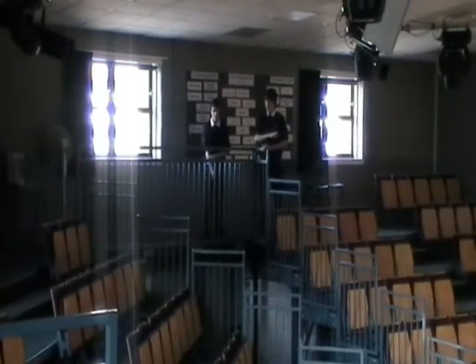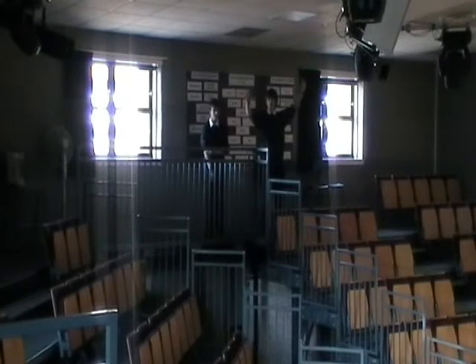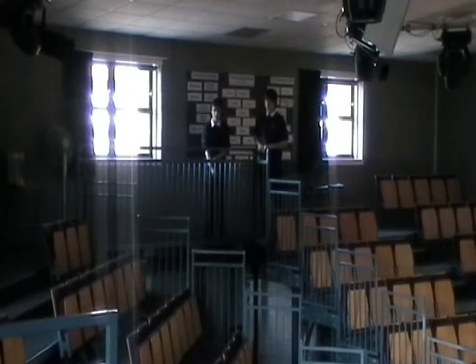One of the major energy loss problems that we have in this college, and within many other colleges in fact, is that heat is coming out of these vents here, as you can see, and is going to stay at 2 metre level around the ceiling, and as it comes to these square grills here, it's lost. Which means that the lower portion of this building isn't being heated, which is a massive energy waste.